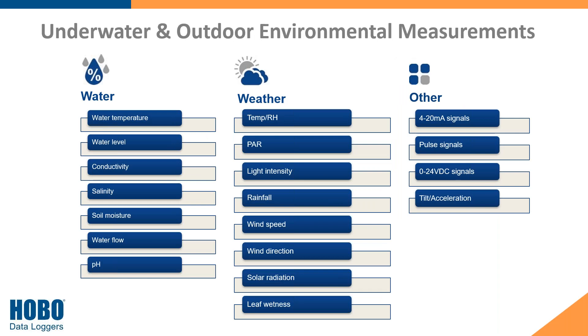We also have outdoor and environmental measurement options. While many are designed for outside environments, you can certainly use them indoors — for example, in a cold room, storage room, or warehouse. For weather, we can capture typical meteorological data: temperature and RH, PAR, wind speed, direction, rainfall, solar radiation, and leaf wetness. We can also capture analog signals — 4–20 milliamp, pulse, or DC voltage — from third-party sensors. It's just a matter of setting up the scaling factor based on the sensor's min/max output, and our data logger will scale that linearly.